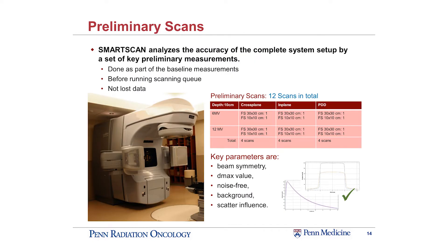One of my favorite things about the SmartScan software is the incorporation of preliminary scans. This is something I've done and taught my residents to do — before you think your setup is right and you're ready to start scanning, just do a couple of preliminary scans before you launch your scanning queue. SmartScan takes that and instead of making it good practice, it makes it standard practice. It's done as part of the baseline measurements, and it tells you what parameters from the LINAC it requires. Once you beam on, it detects the beam and starts running these preliminary scans. For 6X, there are a couple of profiles and PDDs, and it lets you know your setup is good. It's also not lost data — if you confirm these are good scans, it'll remove those respective items from your scanning queue. So there's no lost time.